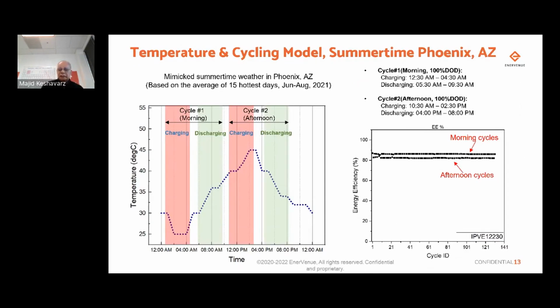We've done more thermal studies, so looked at real life testing. We built the cells and placed them in environmental chambers and programmed the chambers, trying to mimic, for example, Phoenix, Arizona. We got the temperatures from Weather Channel and basically programmed the chambers. The blue trace is the temperature. The low is around 25 and high in this case is 46 Celsius or 114 Fahrenheit. So we are running 2 cycles throughout the day, charge, discharge, and charge, discharge again. One is in the morning, one is in the afternoon.